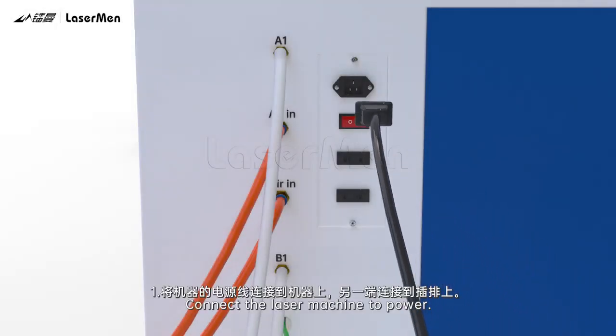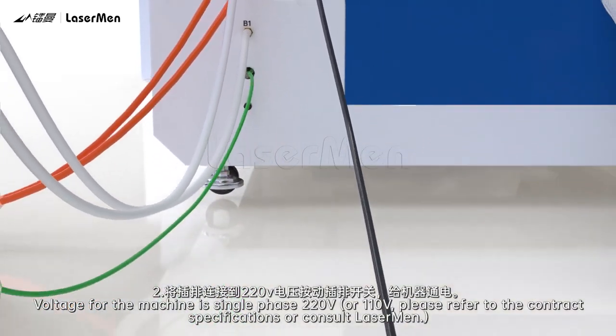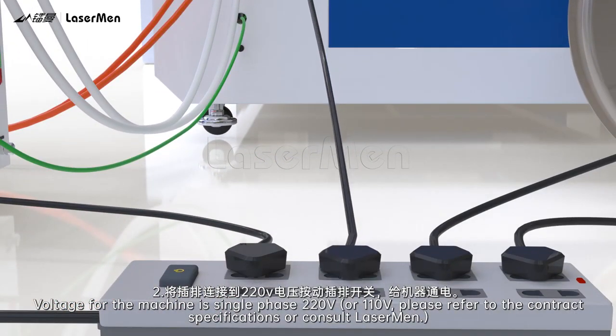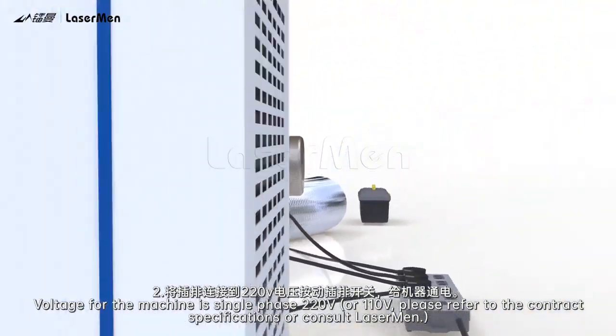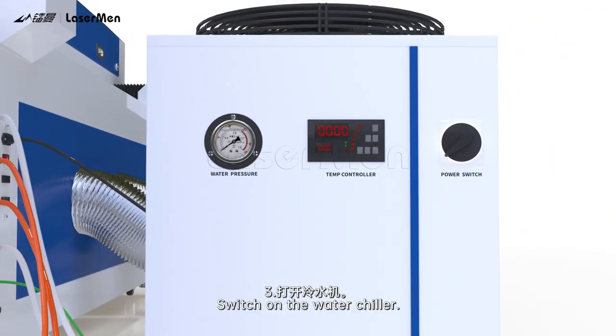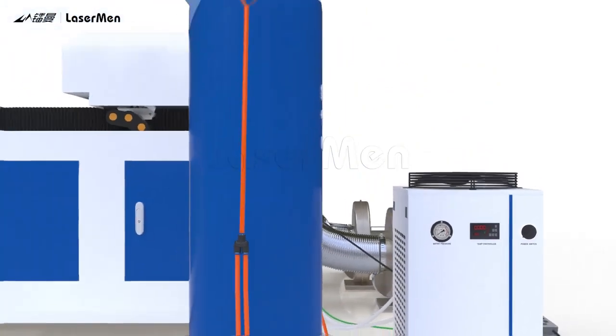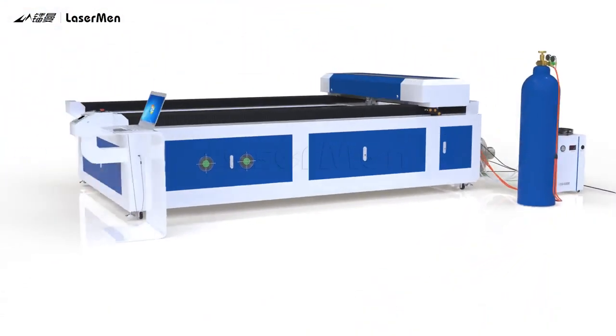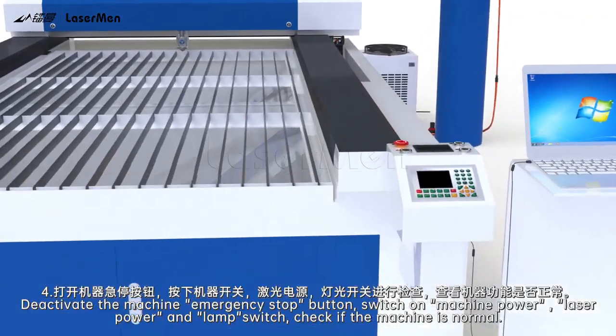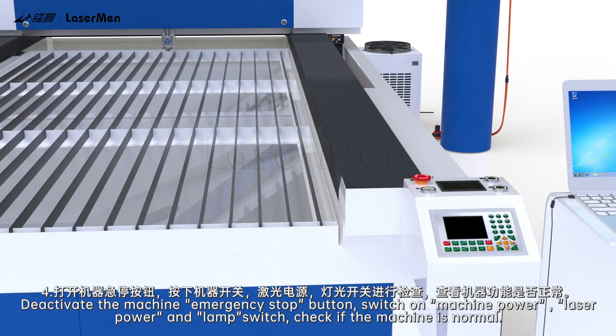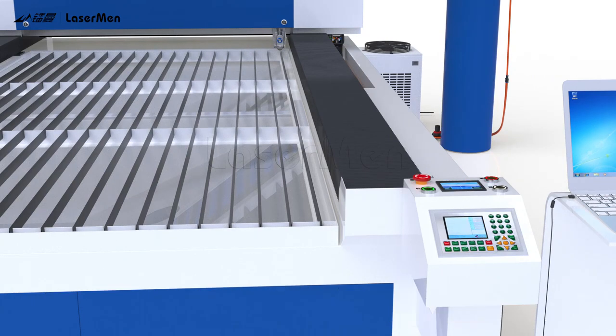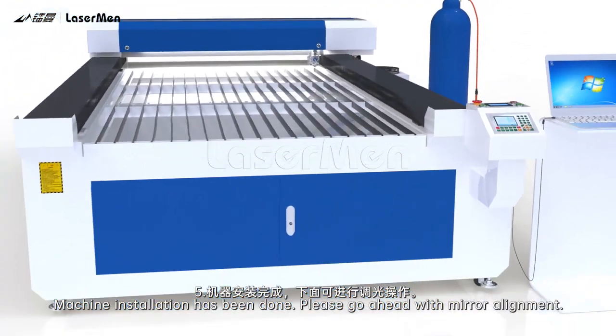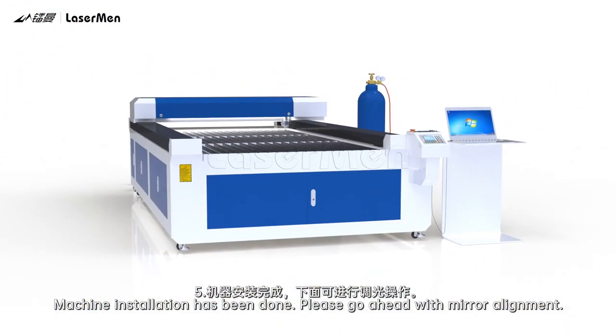Machine testing. 1. Connect the laser machine to power. 2. Voltage for the machine is single phase 220 voltage or 110 voltage. Please refer to the contract specifications or consult LaserMen. 3. Switch on the water chiller. 4. Deactivate the machine emergency stop button. Switch on machine power, laser power and lamp switch. Check if the machine is normal. 5. Machine installation has been done. Please go ahead with mirror alignment.